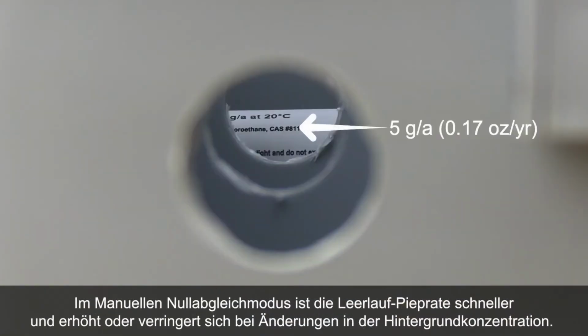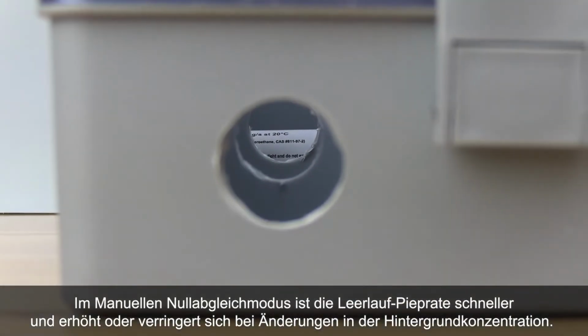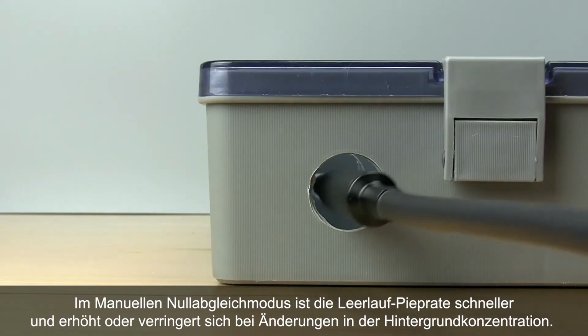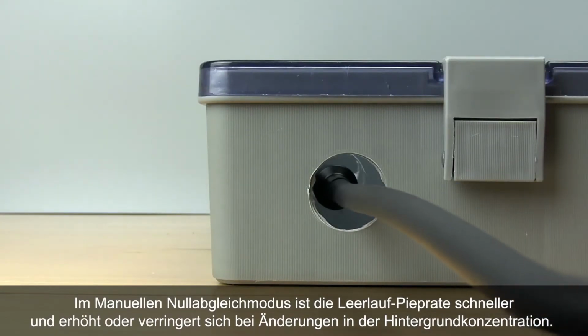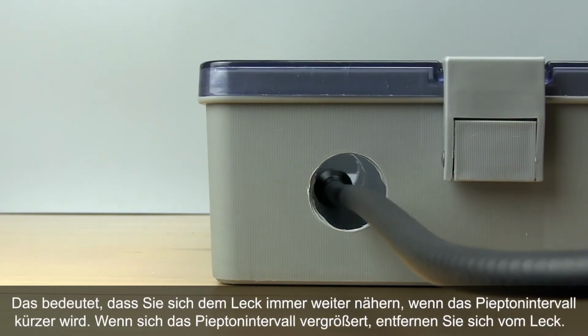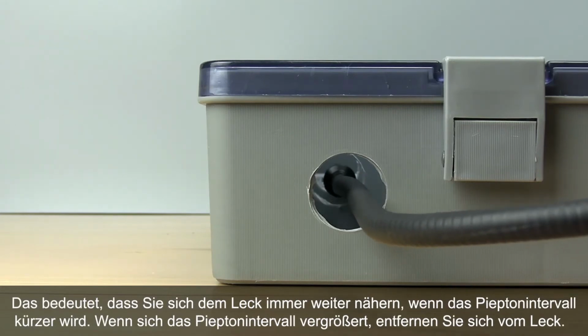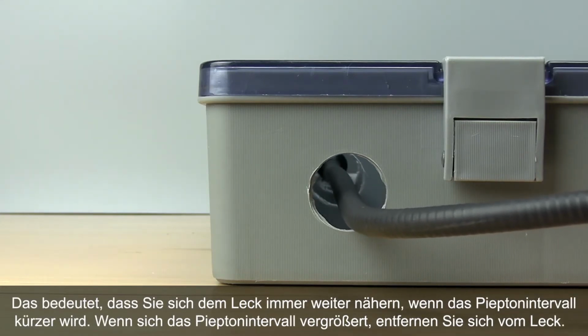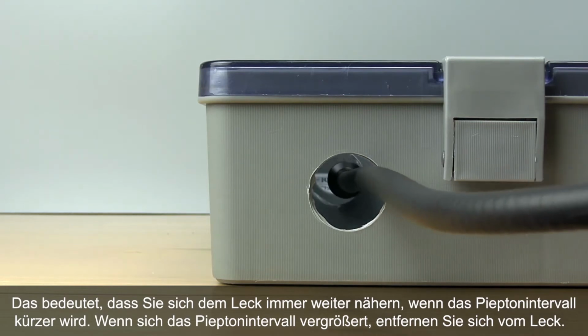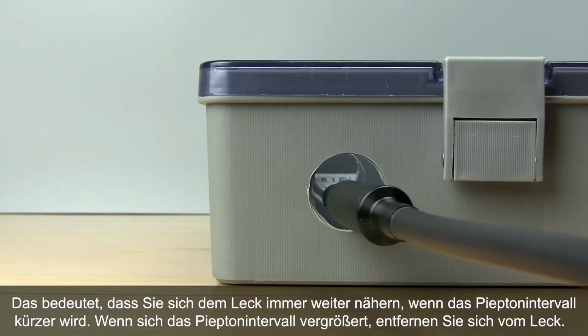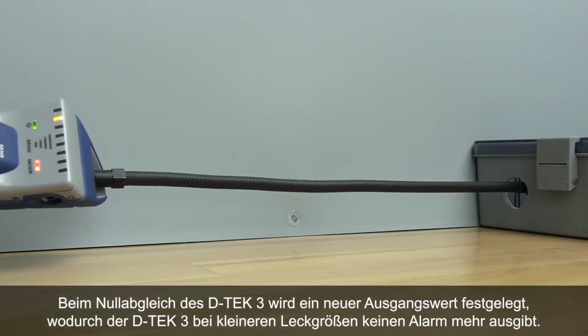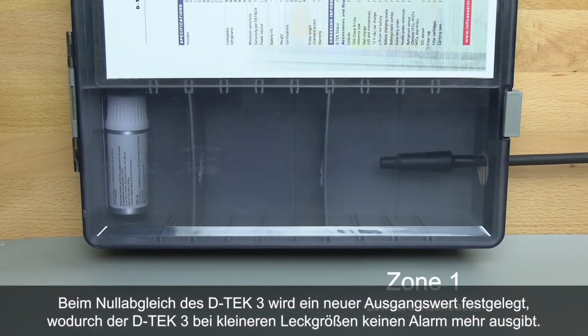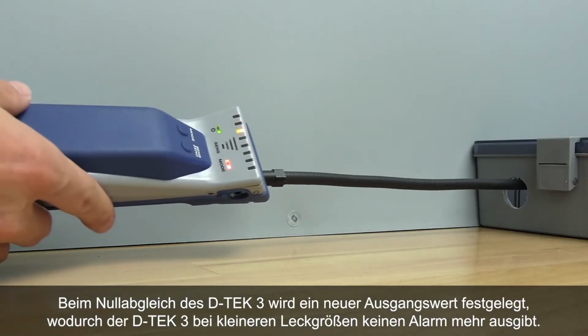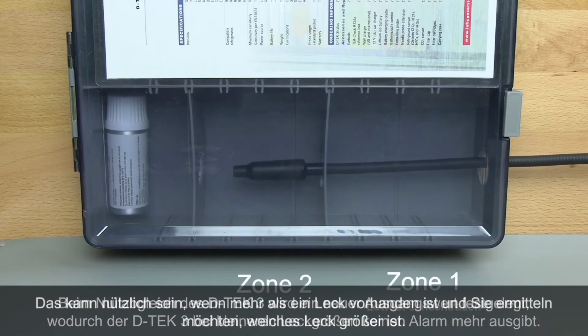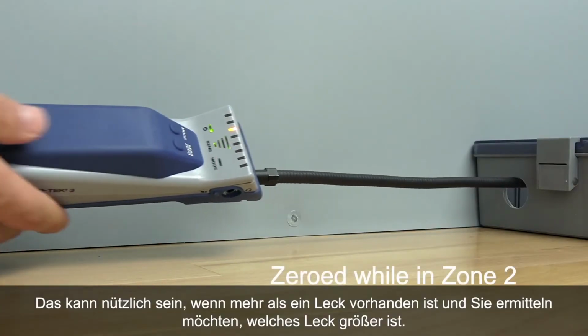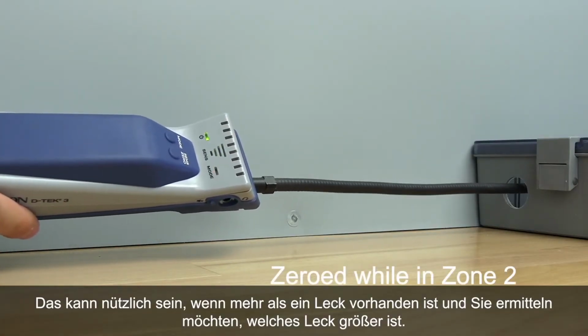While in manual zero mode, the idle beep rate is faster and increases or decreases with changes in the background concentration. This means that if the beeping quickens, you're closer to the leak. If the beeping slows, you're further away. Zeroing D-TEK-3 sets a new baseline, so D-TEK-3 will not alarm on a smaller leak size. This can be useful when you have more than one leak and you'd like to identify which leak is larger.